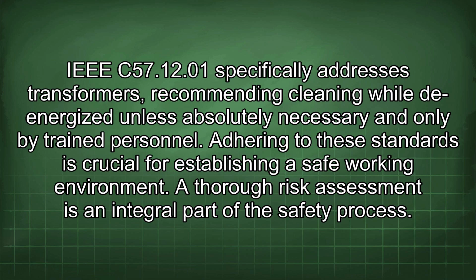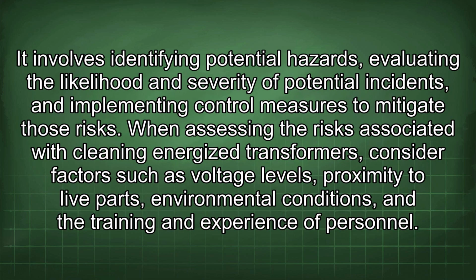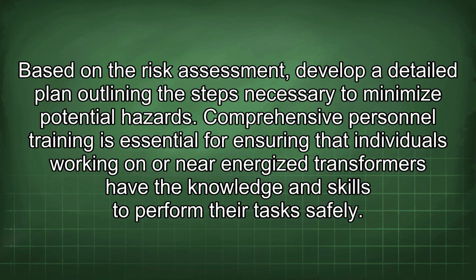A thorough risk assessment is an integral part of the safety process. It involves identifying potential hazards, evaluating the likelihood and severity of potential incidents, and implementing control measures to mitigate those risks. When assessing the risks associated with cleaning energized transformers, consider factors such as voltage levels, proximity to live parts, environmental conditions, and the training and experience of personnel. Based on the risk assessment, develop a detailed plan outlining the steps necessary to minimize potential hazards.